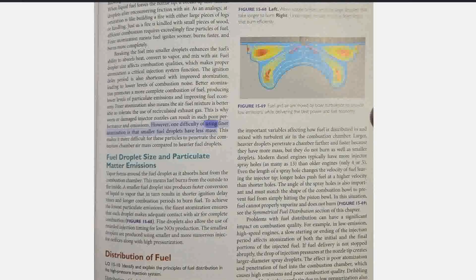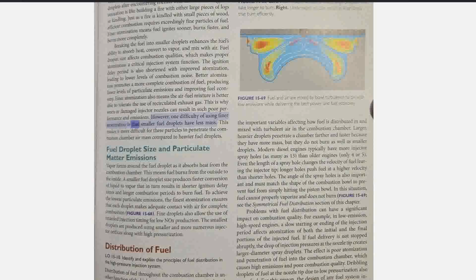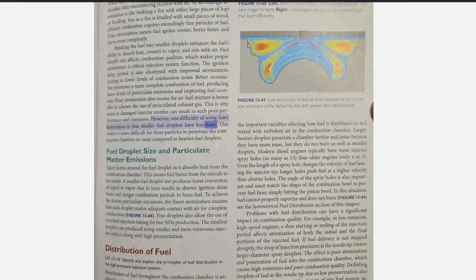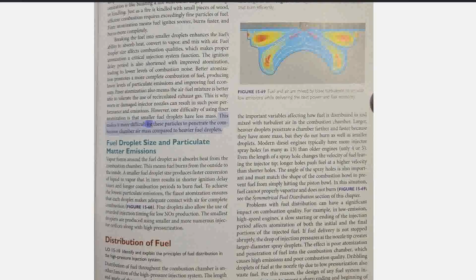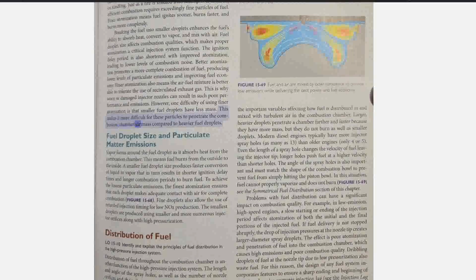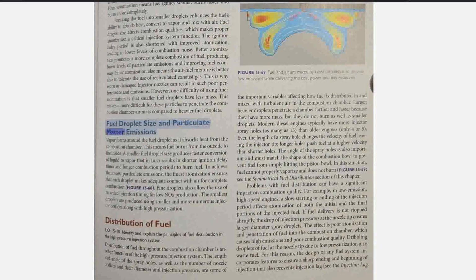However, one difficulty of using finer atomization is that smaller fuel droplets have less mass. This makes it more difficult for these particles to penetrate the combustion chamber air mass compared to heavier fuel droplets. Fuel droplet size and particulate matter emissions. Vapor forms around the fuel droplet as it absorbs heat from the combustion chamber. This means fuel burns from the outside to the inside.